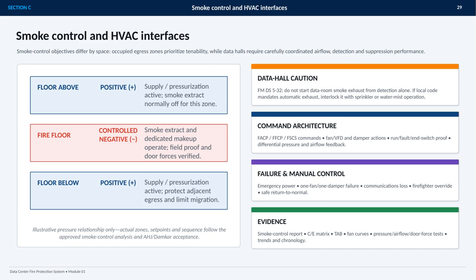The fire floor is controlled negative, while the floors above and below remain positive. On the fire floor, smoke extraction and dedicated makeup air operate together, with field verification of airflow, pressure, and door forces. Adjacent floors use supply or pressurization to protect egress and limit smoke migration. This is an illustrative relationship only. Actual zones, set points, and sequences must follow the approved analysis and authority acceptance.